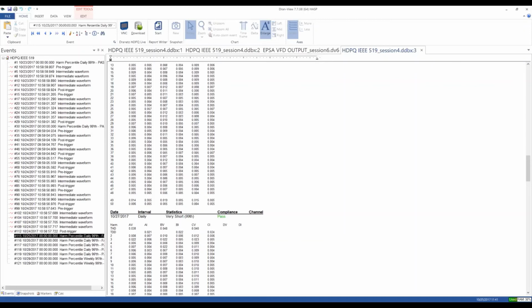Thank you. So what that means is that, usually within a geographic region to date, there hasn't been a requirement to do both. It's been either or, and the instruments are set up for that. That being said, DranView can do some post-processing and produce an EN 50160 report, but the instrument cannot do both EN 50160 and the IEC and the IEEE simultaneously. And it's important to note, for other things on the IEC and the IEEE, one of the reasons why we have those 2 monitoring modes is that each of them has slightly different settings when it comes to limits for interruptions and things like that. So that's the reason for that.